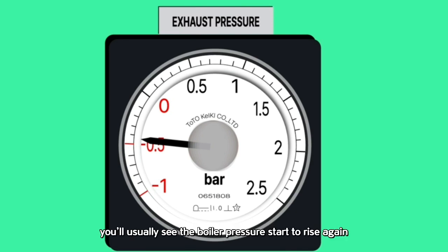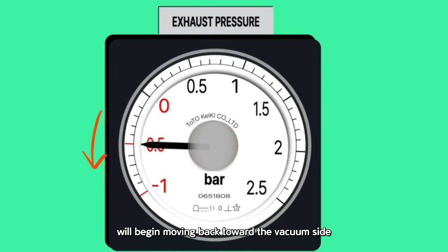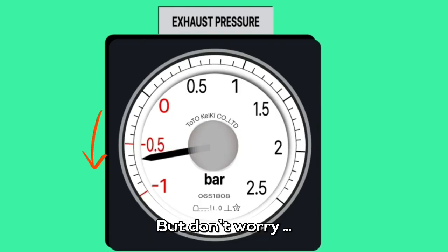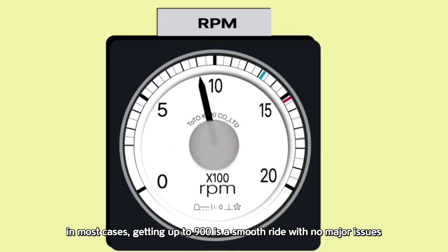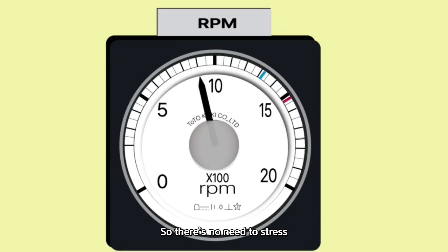After waiting a bit, you'll usually see the boiler pressure start to rise again, and when that happens, the exhaust pressure gauge will begin moving back toward the vacuum side. That's your signal. You can start increasing the RPM again, step by step, until you reach your target of 900 RPM. But don't worry, in most cases, getting up to 900 is a smooth ride with no major issues. So there's no need to stress, just stay calm and follow the process.